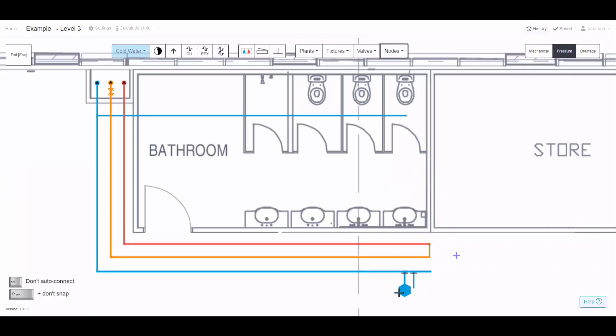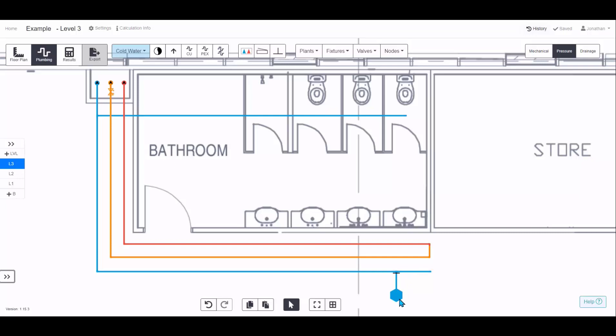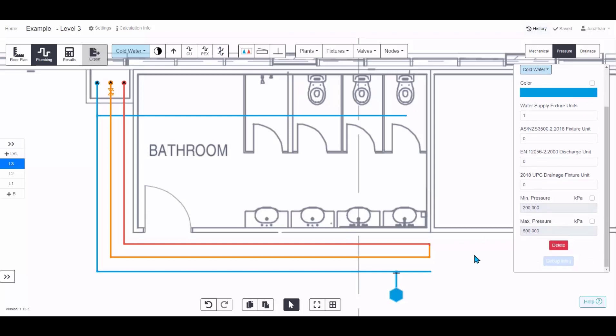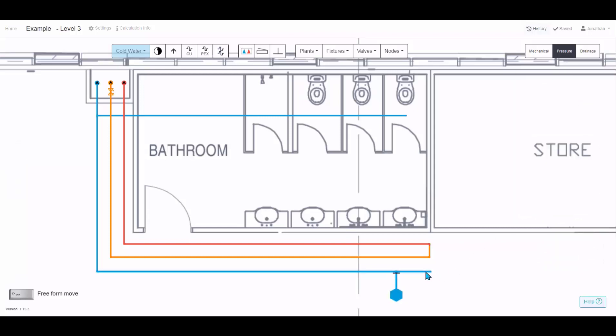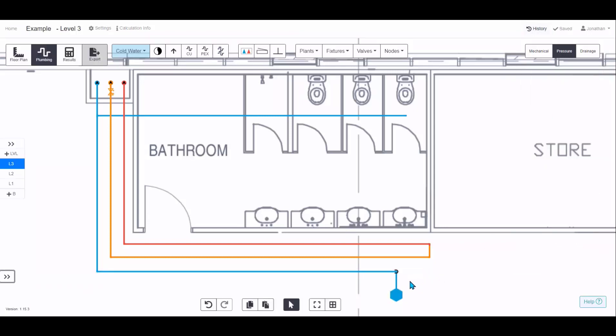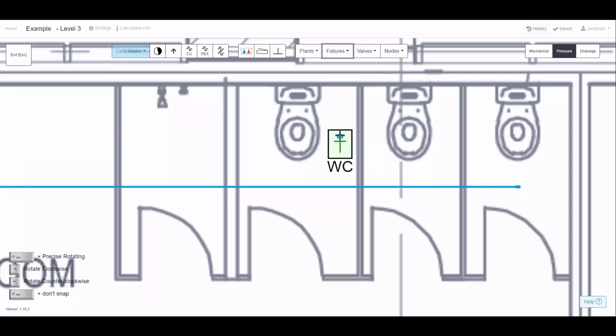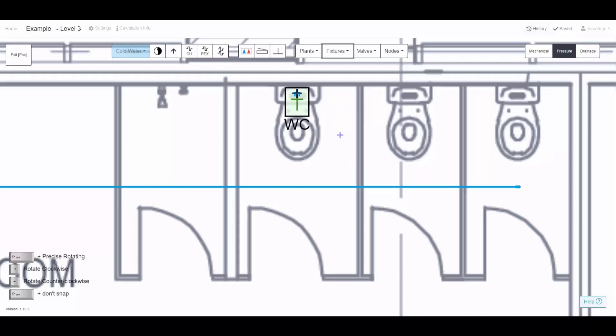For a future fit-out or a fixture type that doesn't exist in the library, give it a name and enter the fixture units or loading units — it will contribute to your design calculations. For fixtures that do exist, choose from the drop-down menu, rotate with the arrow keys, and stamp it where the architect is showing it.